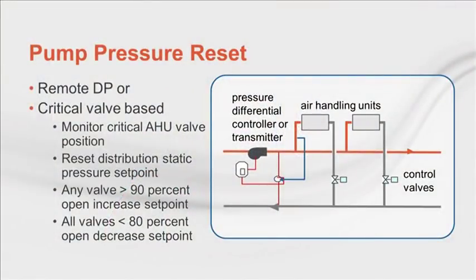So valves are seeing lots of different pressures all the time. As an aside, this is one reason why there is a movement to install pressure-independent valves in variable flow systems, to keep the valves from having jittery control. A remote differential pressure sensor provides information about the average load downstream of its location. The control resets the pump pressure setting downwards until one valve or tertiary pump is nearly wide open, or to keep the remote differential pressure at set point.